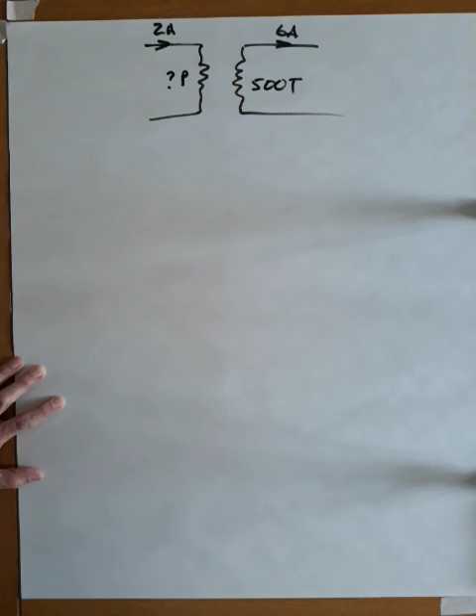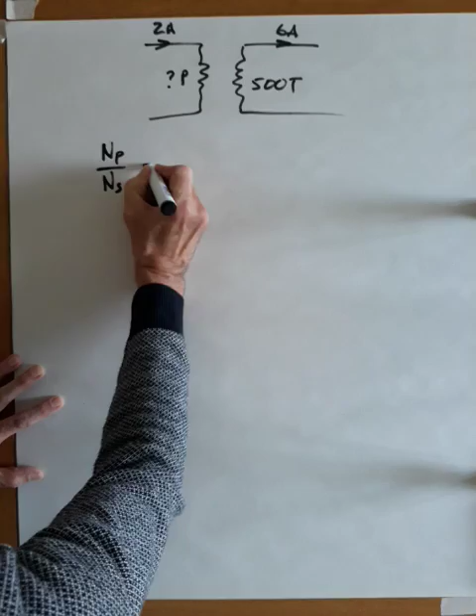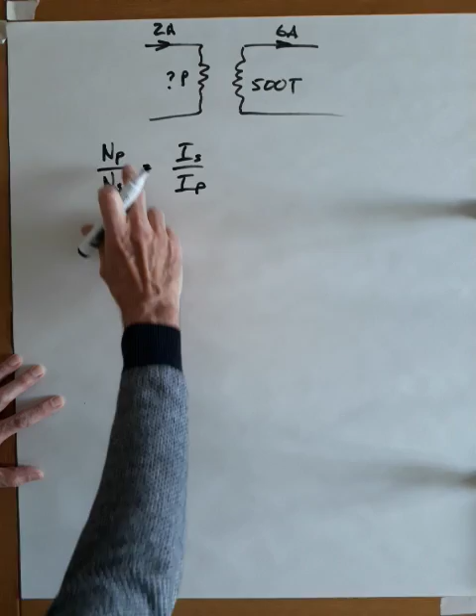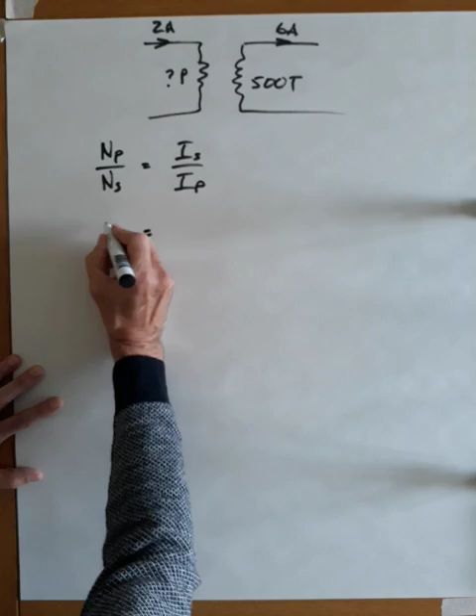The formula is going to involve current and turns, so you can only use two at a time. NP over NS equals IS over IP. The primary turns is what we want to find, so do a quick transposition - that moves to the top. Primary turns equals IS times NS over IP. Put the numbers in: 6 times 500 over 2 is 1500 turns. Hope that made sense.